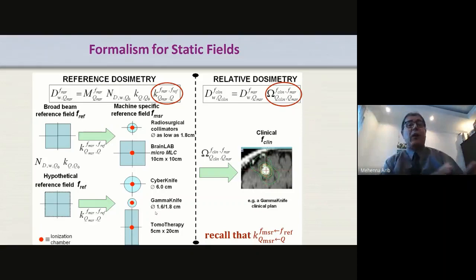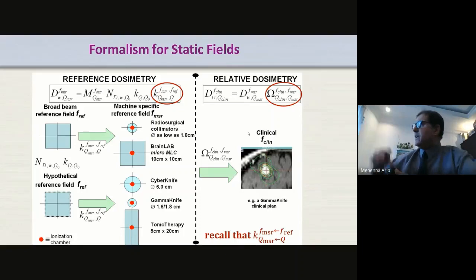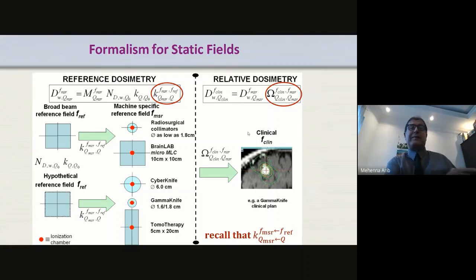So this is the machine-specific reference field. Now when you go to the treatment of the patient, you have what we call the small field size. So just make a difference between the MSR field, which depends on the machine, and the small fields, which are the fields that you are applying to the patients. In that case, you know that the tumor does not necessarily have rectangular or square or cylindrical fields, it's an arbitrary field size. In that case, you have to convert the dose that was measured for the MSR field to the dose that will be delivered to the patient. In that case, you apply what you call a field output factor.